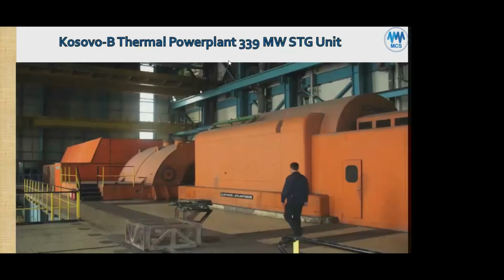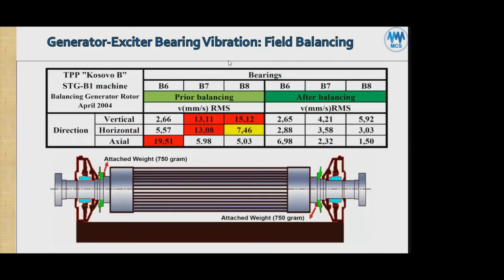Okay. So now we'll look at a case history in Kosovo, thermal power plant. It's a 339 megawatt thermal power plant, and the problem is in the generator and the exciter bearing next to it. So this generator, 339 megawatts, was field balanced in its bearings using the steam turbine to drive it, obviously.